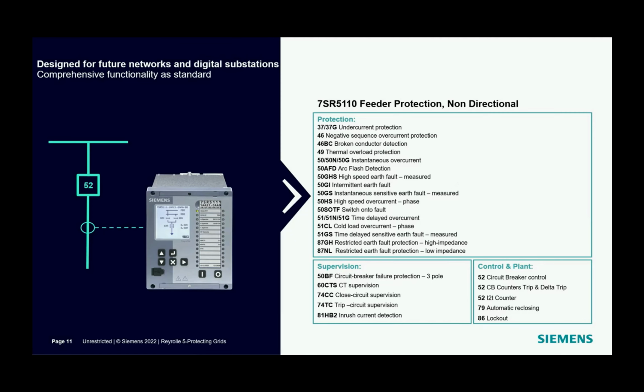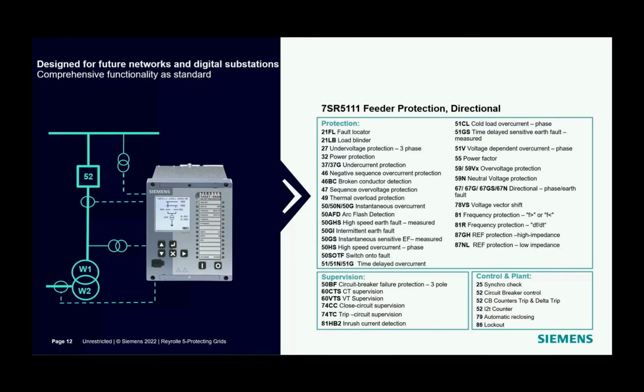7SR5111 are directional overcurrent and earth fault relays. The main difference to the CT-only version 7SR5110 is, by means of hardware, the VT input. So you have CT plus VT here. This brings the directional element to all applicable functions and enables the other voltage-based functionalities, as you can see in the table. With the directional element and all voltage-based functionalities, 7SR5111 is designed for use in interconnected systems at medium voltage level.